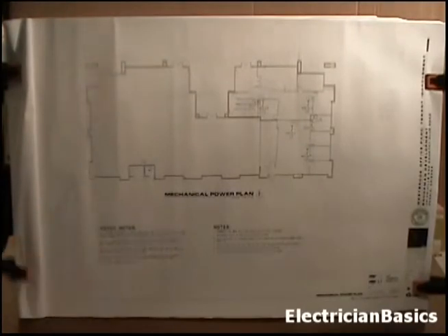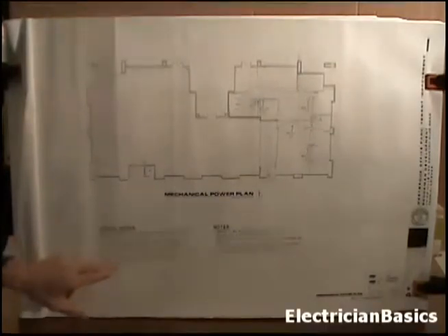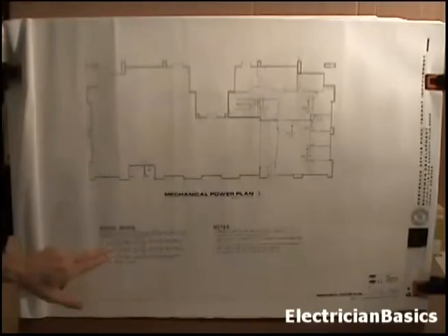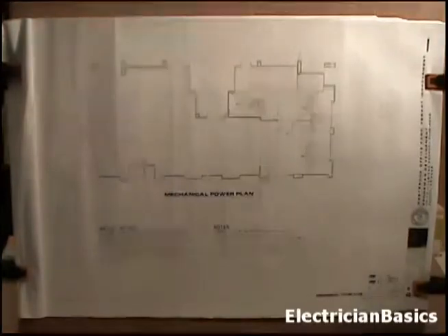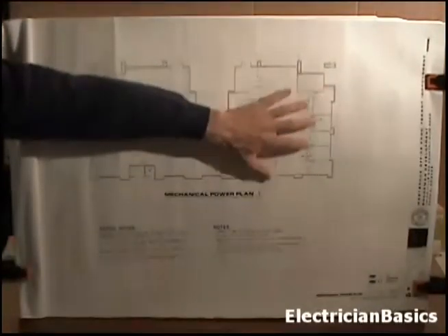It goes into detail on these. Now I don't want to read them, it's a lot of numbers, but to get into it, it tells you the conduit. It uses number 8 wires and a 10 ground from panel as noted. It tells you the type of fuses and to use a fuse disconnect for these. So we're going to zoom into this part of the print now.